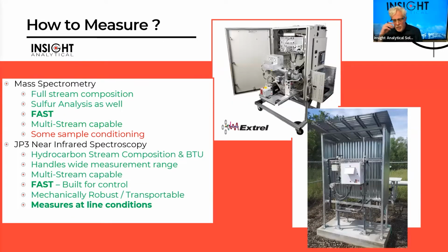Another method that gets used, and we've seen come up on the flare gas side of things, especially in the U.S. with EPA requirements, is mass spectrometry. So things like the Extrel mass specs. They'll give us a full stream analysis. They'll give us a sulfurs analysis as well. They're fast. They're multi-stream capable, so they can be used for process control in these applications. But again, small inlets, so streams that are physically difficult to condition to make suitable for the analyzer can be especially problematic for some of these types of devices.